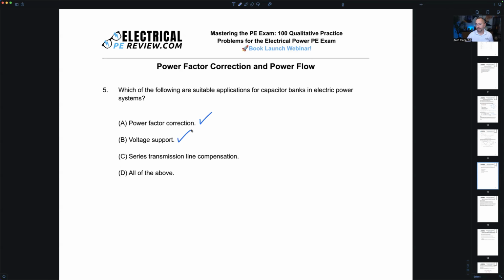How about C? What is series transmission line compensation? So typically capacitor banks, how do we install them most of the time? Do we install them in series or do we install them in parallel, or typically we call that shunted? Yeah, we usually shunt them, said Caleb. Well, series compensation is a very specific application of capacitors where we actually install them in series with our transmission line conductors. If you're in our online class for the PE exam, class 11 end of life class test has an excellent quantitative problem on series transmission line compensation using capacitors.